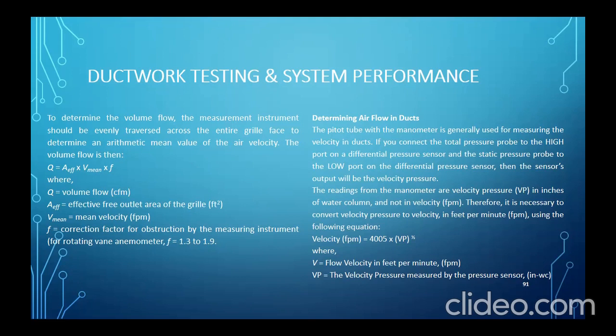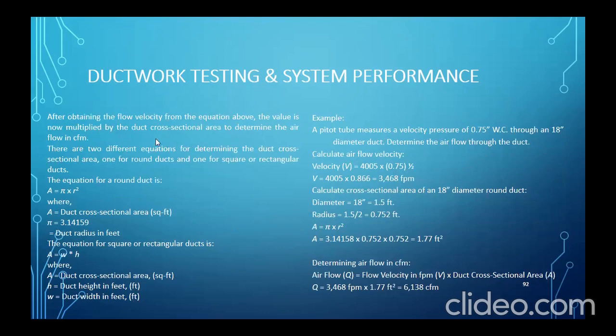So velocity in feet per minute is V = 4005 times Vp to the exponent 1/2, where V is the flow velocity in feet per minute and Vp is the velocity pressure measured by the pressure sensor in inches of water column. Now, after obtaining the flow velocity from the equation above, the value is multiplied by the duct cross-sectional area to determine the airflow in CFM. There are two different equations for determining the duct cross-sectional area, one for round ducts and one for square or rectangular ducts.